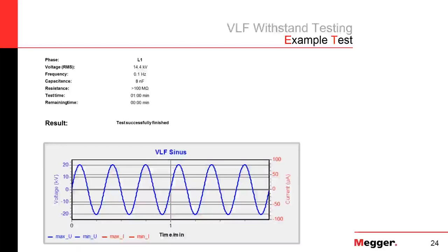So this would be an example of some test results from VLF testing. You can see on the picture there, it's just a constant sine wave over time. And in this case, the test successfully finished. The cable held the voltage for the time applied and did not break down. For this example test, we only held it on for 1 minute, but IEEE does require 30 to 60 minutes. If we held it on any longer, the voltage waveform on the bottom gets too squished to see.